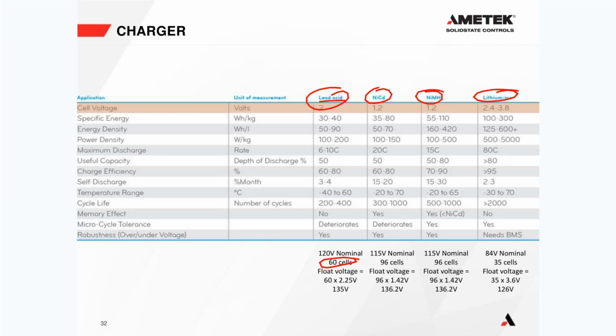That's a 120 volt nominal DC bus. If you look at the data sheet for most lead acid batteries, they say they need to be charged at 2.25 volts per cell at 77 degrees Fahrenheit. So therefore, we have 60 cells times 2.25 volts. That means the float voltage out of the rectifier charger circuit needs to be 135 volts.